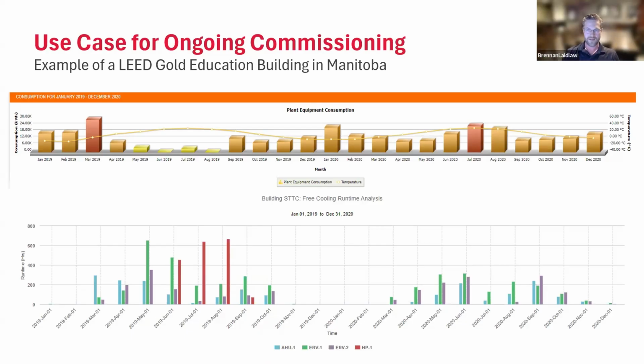And what we found was there was a big difference in energy usage for their mechanical systems in 2019 versus 2020. Not getting into the full details, a lot had to do with how the building was being used. They were using the building in a different way, to a higher capacity, which would cause the mechanical equipment to run a little bit more, and we used a lot less free cooling through the automation as a result. So that's a good example where buildings are being used differently, and it affected their energy through a cascade effect down the line.